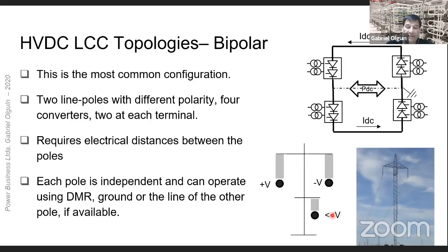The bipolar HVDC is the most common topology. In a bipolar link, two pole lines at different voltage polarity connect four converters, two at each terminal. Due to the plus-minus polarity, the station layout and line tower geometry require electrical distances between the poles, making this topology more expensive than the homopolar. A bipolar link is formed with two monopoles that share the return path, and each pole is independent of the other, except for the neutral and the return path. The main advantage of this topology is the possibility of providing some backup in case of a pole line fault.